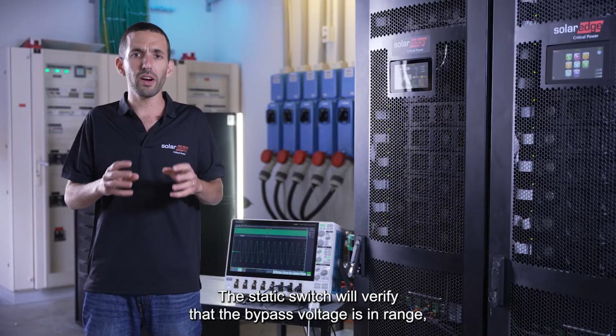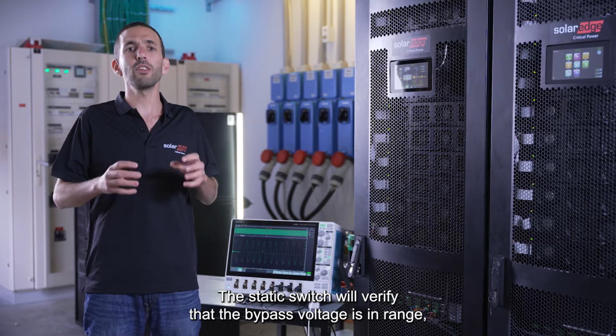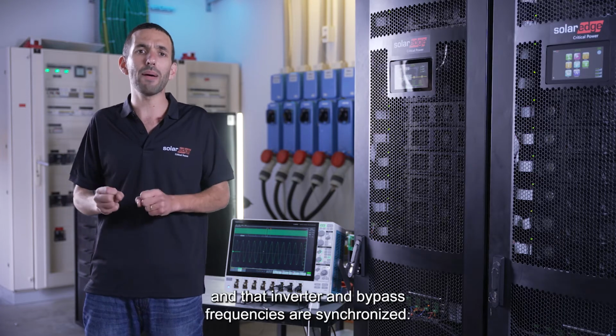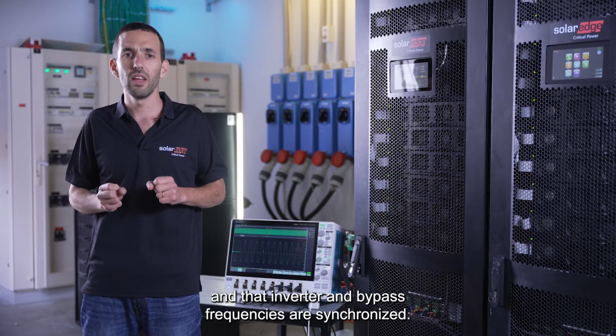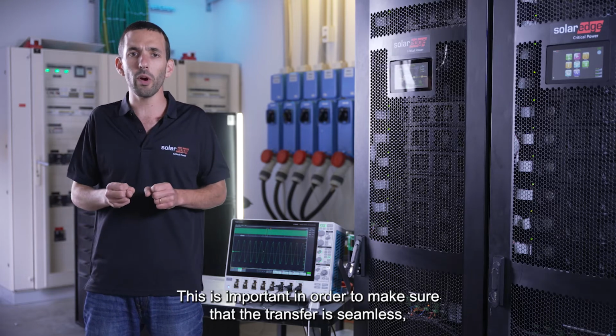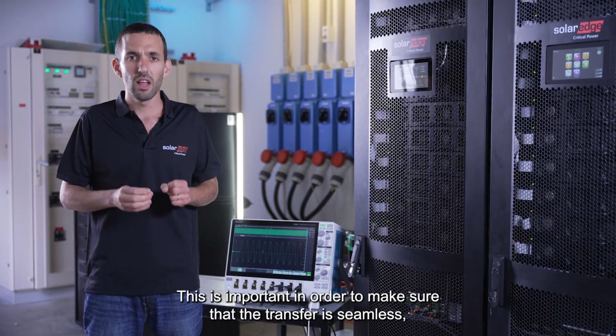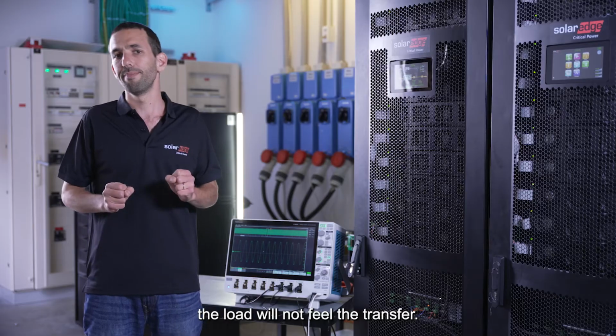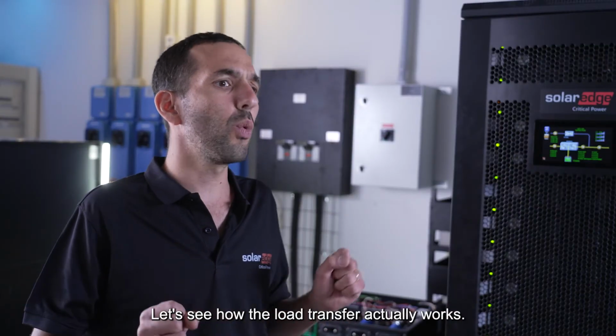The static switch will verify that the bypass voltage is in range and the inverter and bypass frequencies are synchronized. This is important in order to make sure that a transfer is seamless. The load will not feel the transfer. Let's see how the load transfer actually works.